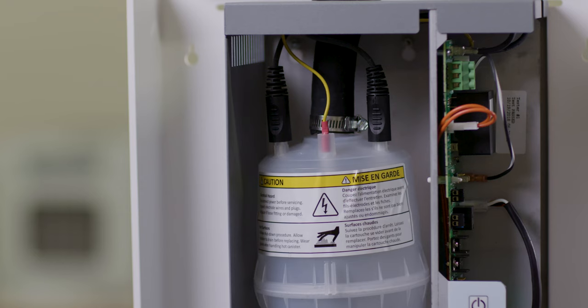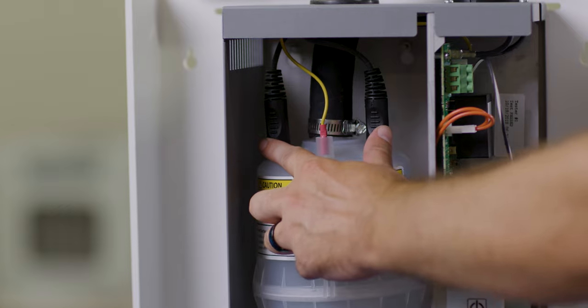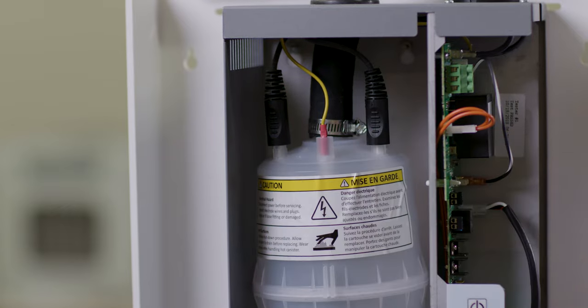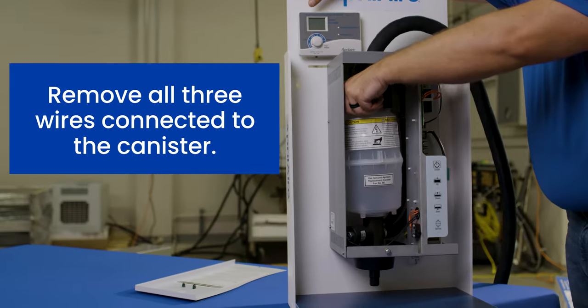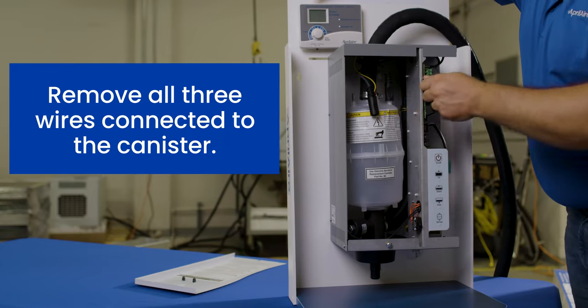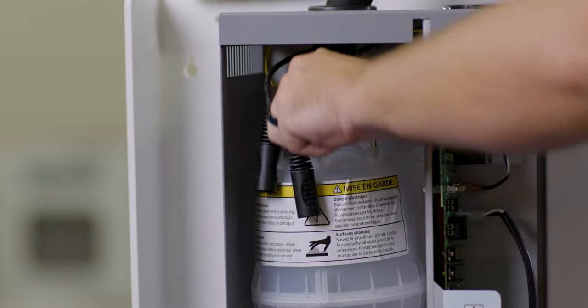On top of the canister, there are two electrode wires with black connectors and a yellow high water pin with a red connector. Pull those off. There's no polarity, so the electrode wires can be reattached to either of the corresponding pins.